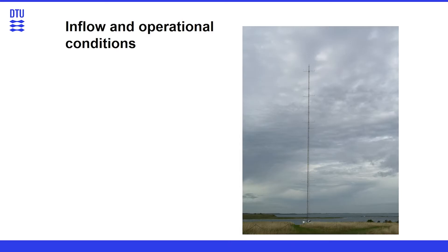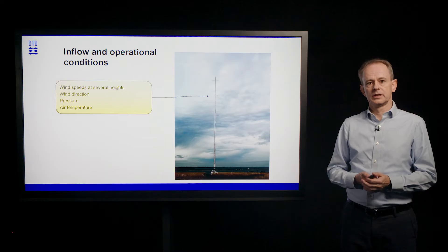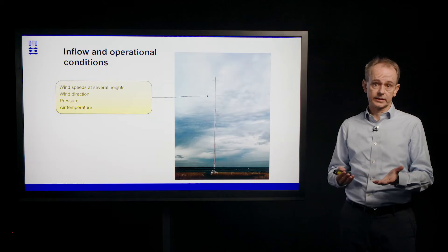In addition to the measured loads and response of the turbine itself, we also need to measure what is the inflow. This is typically measured on a meteorological mast in front of the turbine, where wind speeds are measured at several heights. Wind direction, pressure, and air temperature are measured. It can also be measured with a remote sensing device like a lidar.